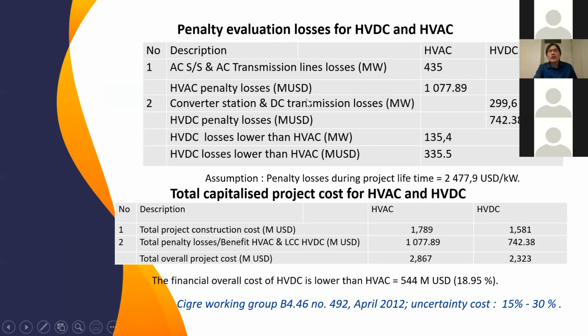So when we convert the losses to money, by assuming a penalty for losses during the project lifetime, let's say like 2,500, this amount, we get the penalty evaluation of losses for HVAC of 1 billion, while for HVDC only 742 million US dollar. So if we combine the project construction costs from the previous calculation and the penalty for losses, or benefit, between AC and DC here, we can see the overall financial cost, construction and losses, of HVDC is lower than HVAC by 18.95%.